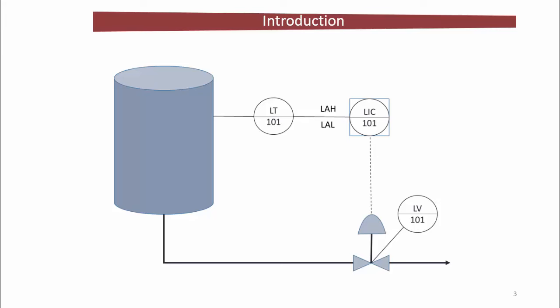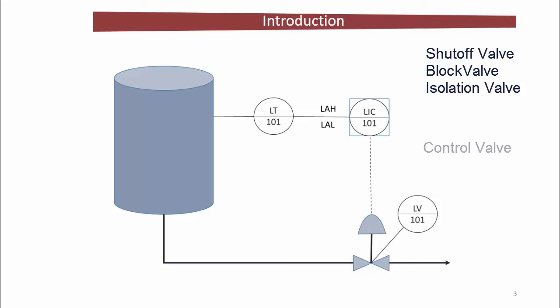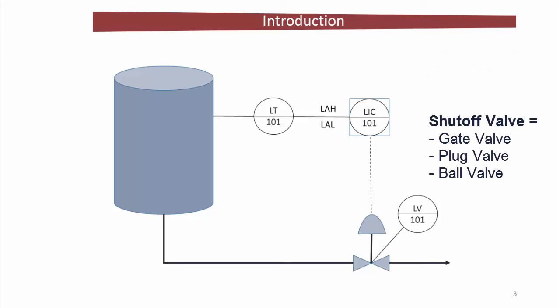The valves used for chemical process plants can be divided into two broad classes depending on their primary function. Shut-off valves, also named block valves or isolation valves, whose purpose is to close off the flow. And control valves, both manual and automatic, which are used to regulate the flow. A valve selected for shut-off purposes should give a positive seal in the closed position and minimum resistance to flow when open. Gate, plug and ball valves are most frequently used for this purpose.